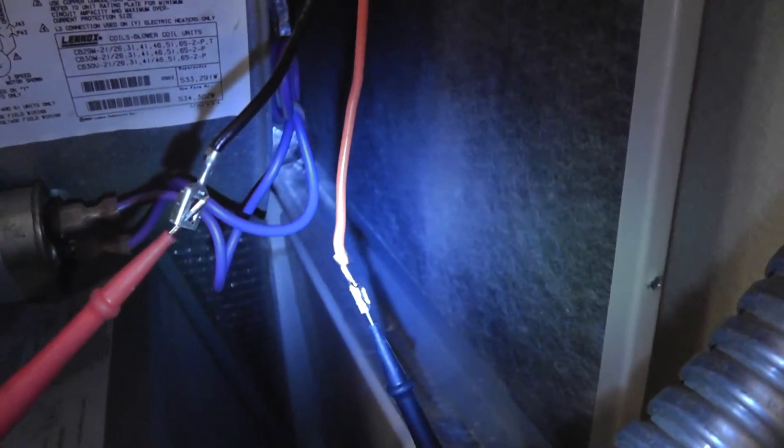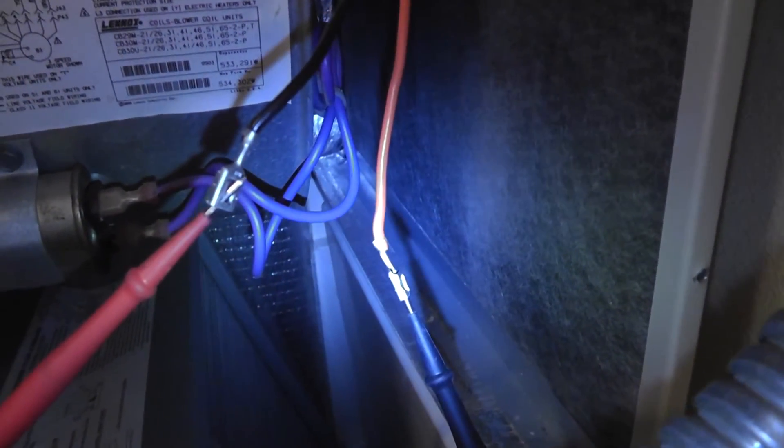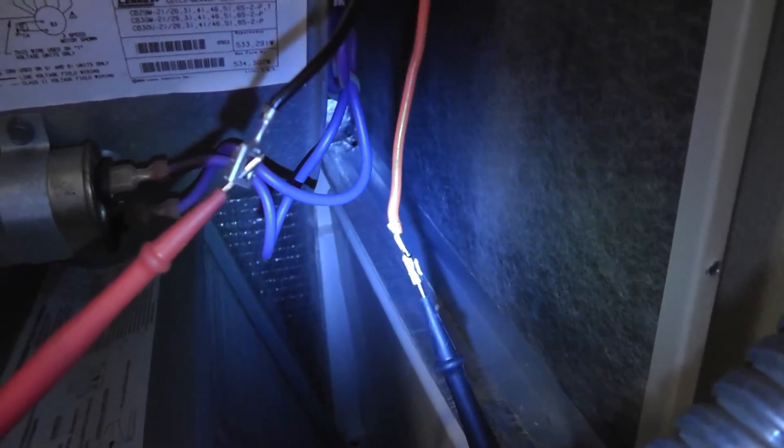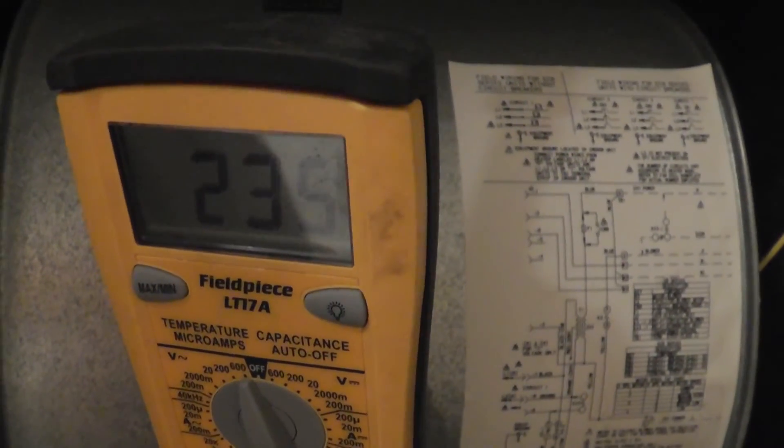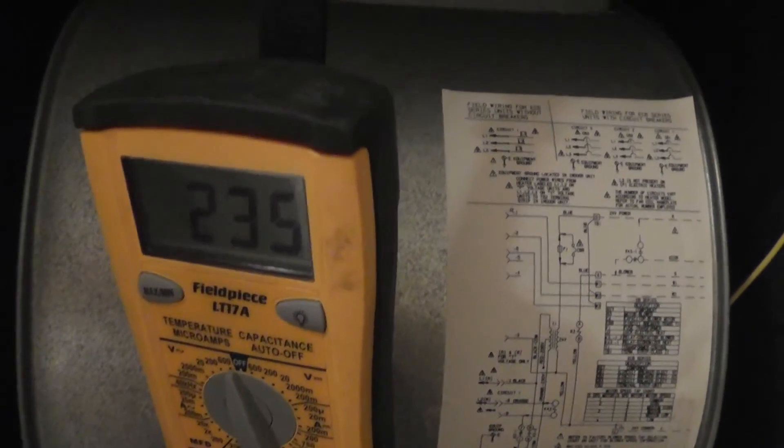So again, we checked it right here at the leads at the motor. We asked for demand for cool at the thermostat. We turned on the fan motor. Doing it the smart way. We got 235 volts.